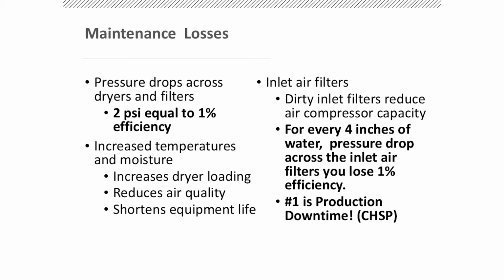The other thing it does is it increases temperature and moisture. If you don't clean aftercoolers and intercoolers on a compressor, no matter what the system, for example, if you have a refrigerated dryer, they've got what's called the 100-100-100 rule. Basically it's designed for 100 degrees Fahrenheit, 100 PSI inlet, and 100 degrees ambient. If you go anywhere outside of those parameters, you'll have to derate the dryer.